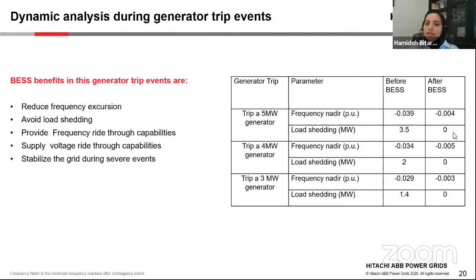Another benefit from BESS, other than reducing frequency excursion or avoiding load shedding in these events, is that the BESS didn't trip during these events. If the BESS would trip during these events, it would make this case more severe. But the technology has frequency ride-through and voltage ride-through capabilities, so it will not trip during this contingency and will not make the case more severe, but provide frequency support and voltage support to stabilize the grid and make the grid more resilient.